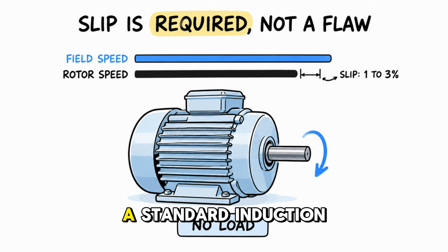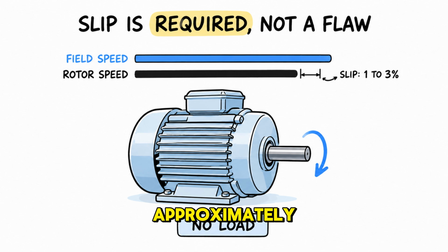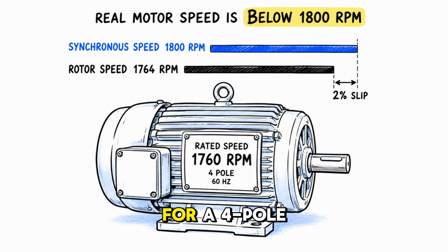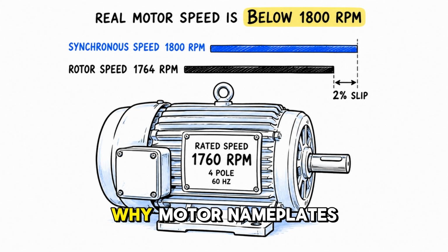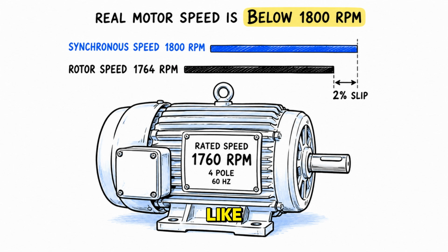At no load, a standard induction motor runs at approximately 1 to 3% slip. For a 4-pole motor on a 60 Hz supply, the synchronous speed is 1,800 RPM. At 2% slip, the actual rotor speed drops to 1,764 RPM. This is exactly why motor nameplates show rated speeds like 1,750 or 1,760 RPM, rather than the theoretical 1,800 RPM.